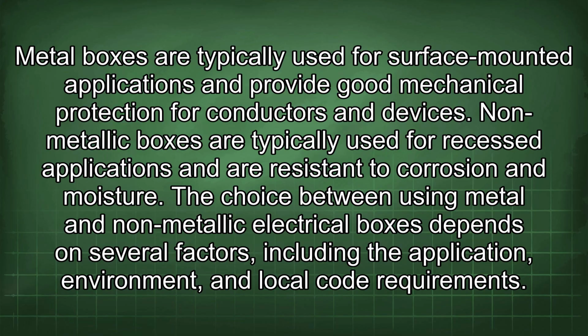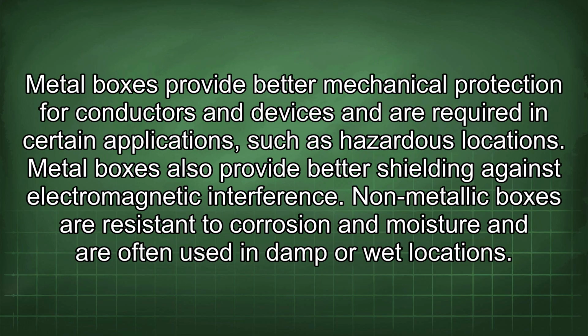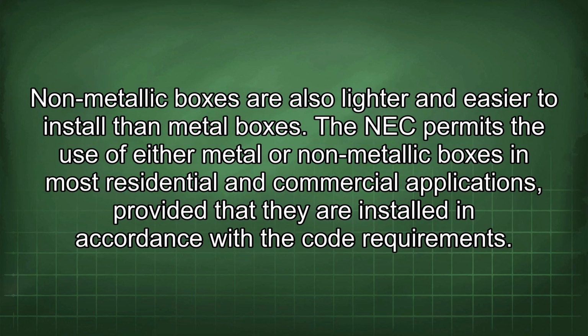The choice between using metal and non-metallic electrical boxes depends on several factors, including the application, environment, and local code requirements. Metal boxes provide better mechanical protection for conductors and devices and are required in certain applications, such as hazardous locations. Metal boxes also provide better shielding against electromagnetic interference. Non-metallic boxes are resistant to corrosion and moisture and are often used in damp or wet locations. Non-metallic boxes are also lighter and easier to install than metal boxes. The NEC permits the use of either metal or non-metallic boxes in most residential and commercial applications, provided that they are installed in accordance with the code requirements.